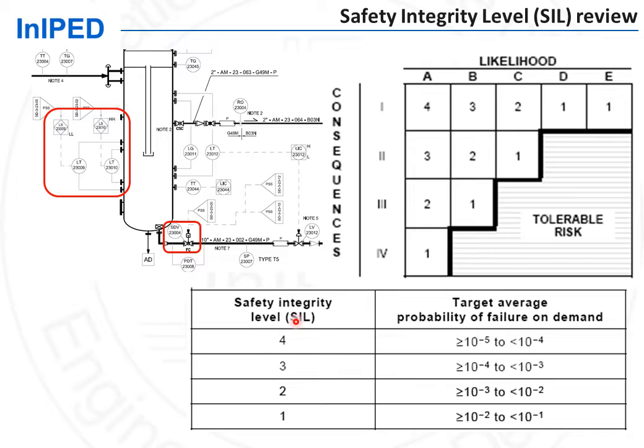If the safety instrumented function is specified a SIL rating, then it will be subject in a second step to a thorough review of the type of equipment — such as the sensor, the controllers, and the final element — and their probability of failure, so that the overall loop, the overall instrumented safeguard, provides the adequate probability of failure on demand. This is called the SIL review.